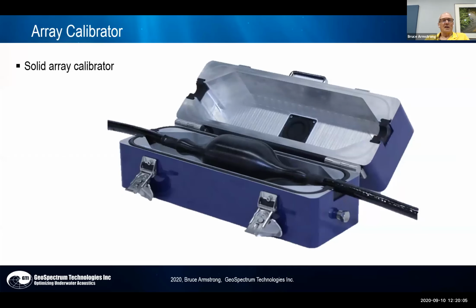You can use this technique to calibrate arrays. So here you've got a case where the box isn't perfectly sealed. You machine a metal box, and you've got some rubber seals where it goes around the cable. It's not important whether you get small leaks, because you're measuring the unknown hydrophone and the reference hydrophone at the same time. So a small leak just creates a slightly lower dynamic pressure.